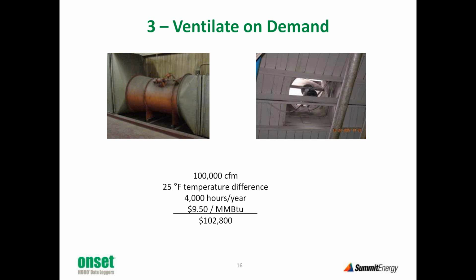And you have to limit the CO2 levels. If you put a whole bunch of people in a sealed space, the CO2 levels will rise to uncomfortable and eventually dangerous levels. So you have to bring in outside air to keep the CO2 level in a safe range. When we say ventilate on demand, what we mean is measure the CO2 level and bring in as much outside air as you have to keep the CO2 level in a safe range.